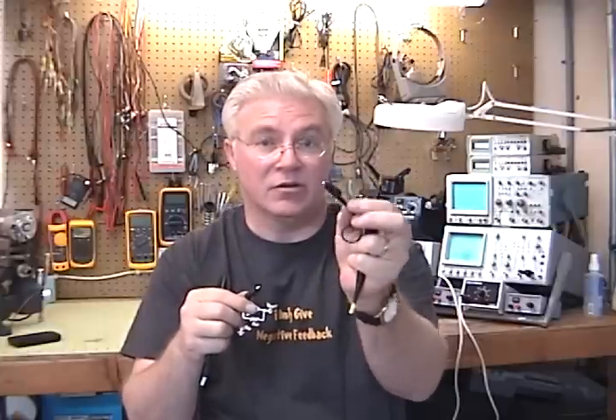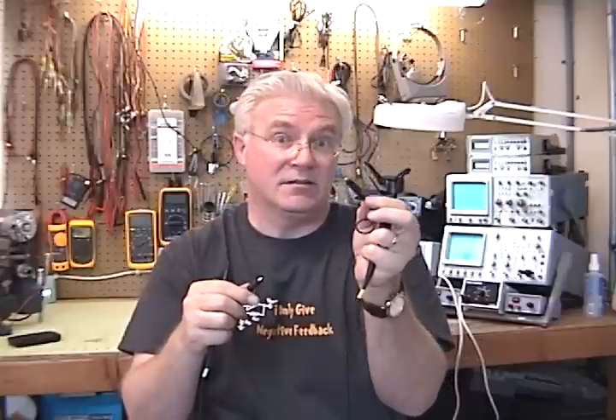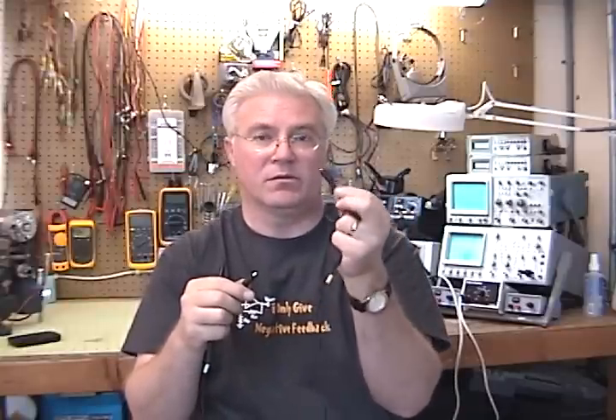And here's another one. It gets a little tricky. If you got your second probe, and like I just said, you hook up this one, you just made that new neutral reference on your secondary to earth mains ground. The other probe is hooked up to ground too. If you got another probe, you want to probe another spot, you hook this up to the same exact spot, and you're fine, because they're at the same potential. But if you decide to hook this second probe, which has a grounding clip to ground, to some other potential on your board, you switch it by accident, and you put this grounding clip at a high voltage reference on your board, you just grounded out your secondary of your transformer. Your isolation transformer's secondary windings just got grounded out through your scope, and that's going to damage your scope and your other equipment. It's going to make a dead short on that secondary. So when you get out a second probe, be careful.